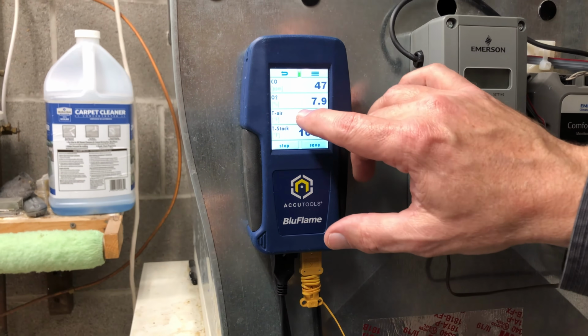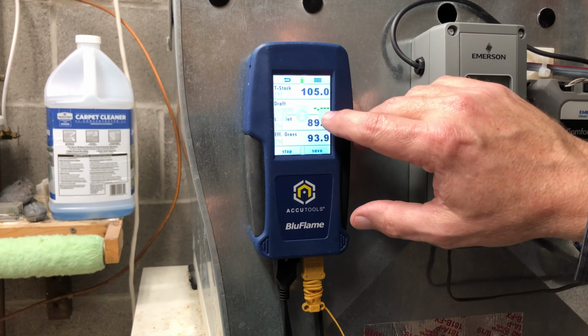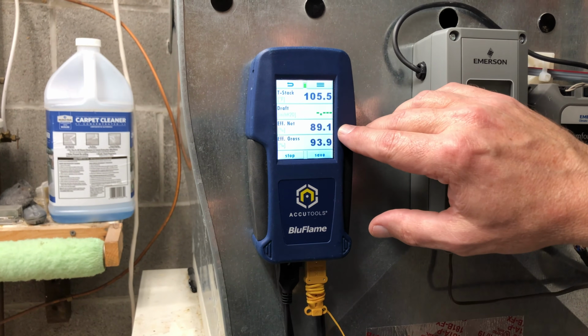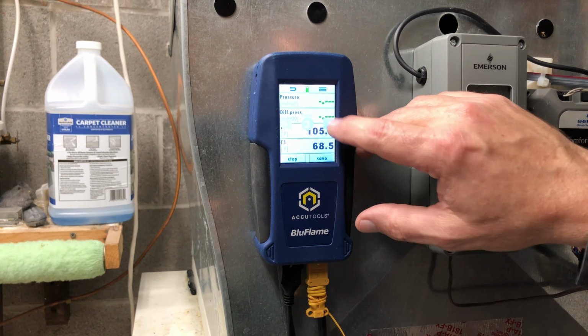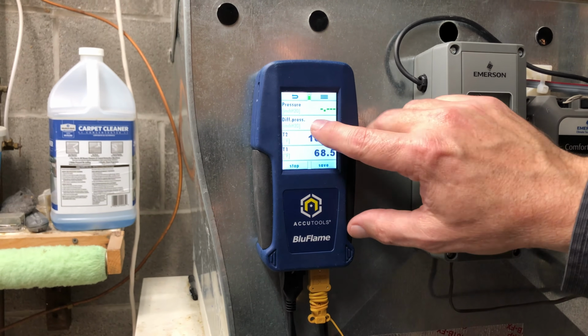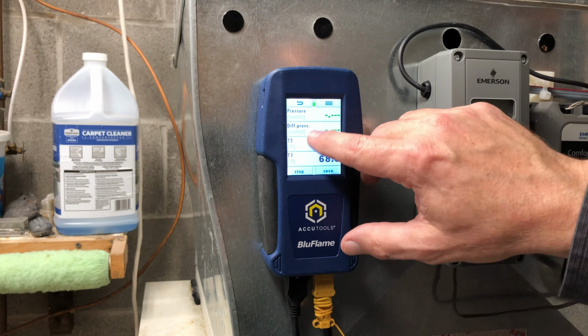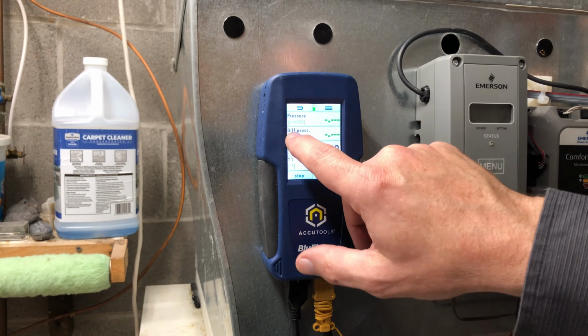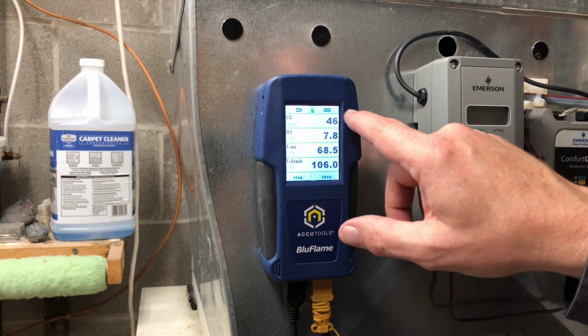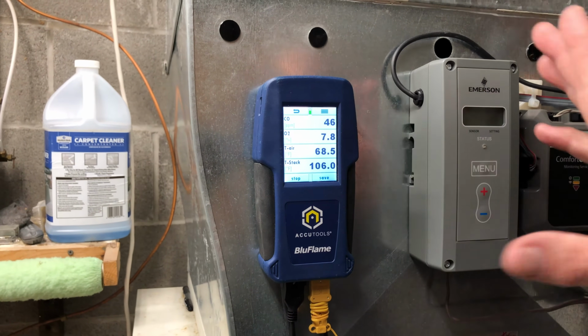I'll just scroll through a couple readings here so we can see them. My stack temperature, my draft, efficiency, net and gross look good. And then I'm going to just take a look at the rest of the readings, see everything else here I want to look at, and I think we're good. So this is just set up with a couple numbers on here, but primarily what I wanted to look at is make sure I'm not making excessive amounts of CO, and those numbers are good.